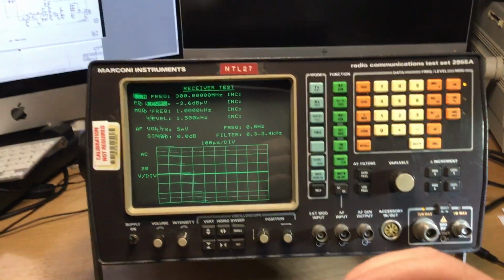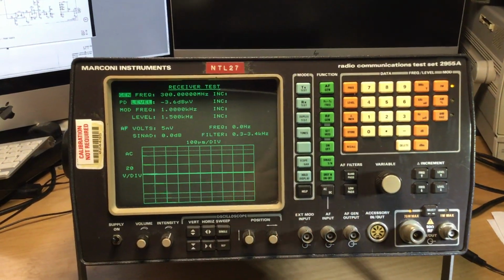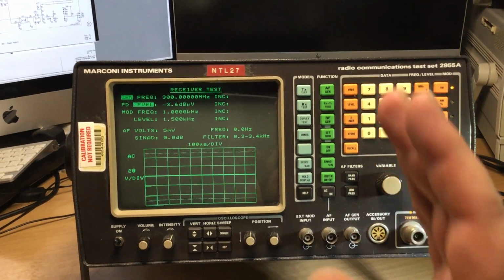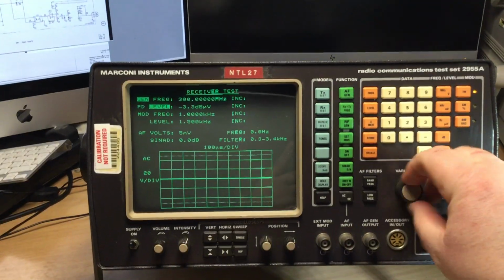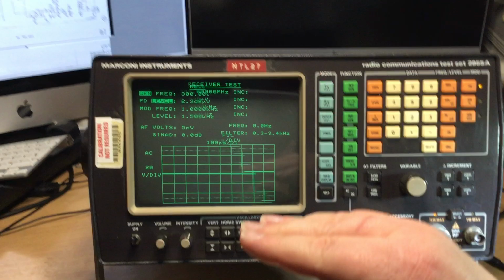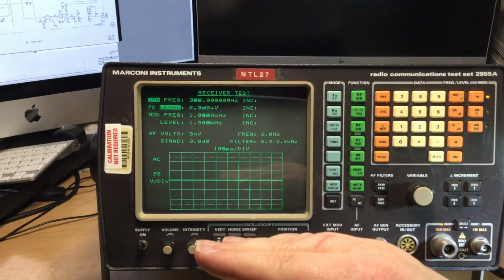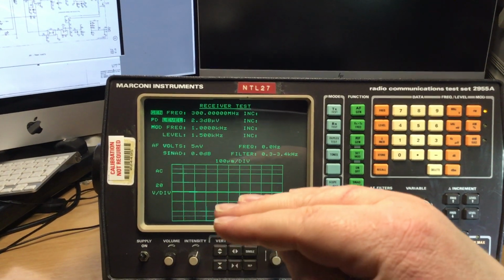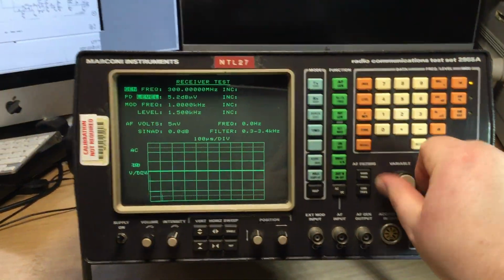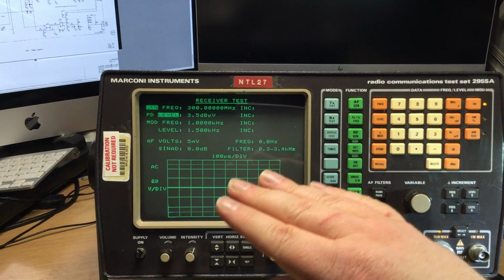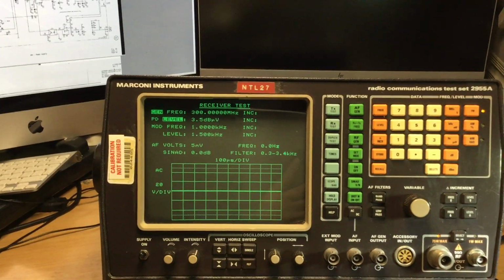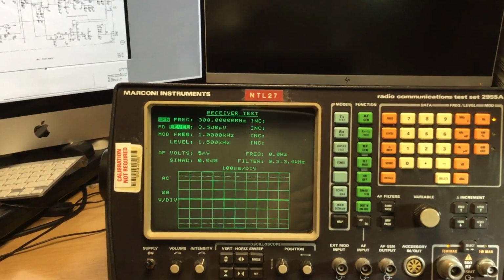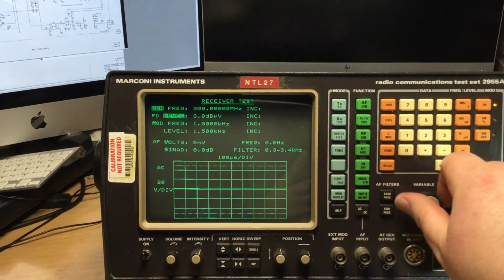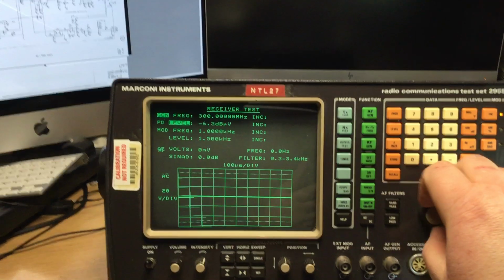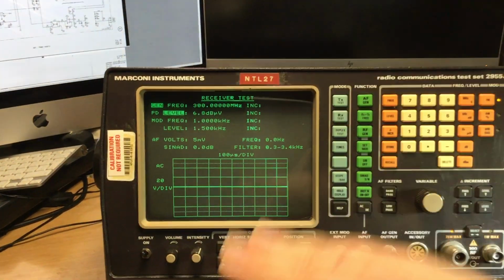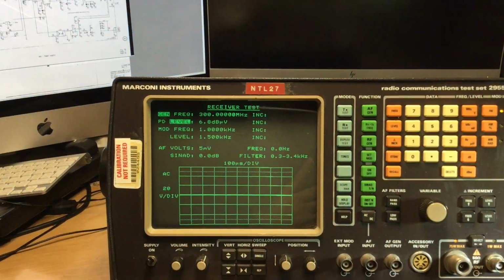But the pin diodes, there's a pin diode attenuator on the signal generator board, which is controlled by the microprocessor with a DC level, and as we adjust the rotary control on the front to a different RF level, in between the steps of the mechanical attenuator, the electronic attenuator, which consists of pin diodes, has a DC control voltage applied to it, and that depends on where we are with the control on here. And that level then changes the attenuation characteristics, the RF attenuation characteristics of the pin diode attenuator, and that's how we get the RF level to change between the physical mechanical steps. So we get a linear sort of control of the RF level, a fine control of 0.5 dB steps or whatever right the way through its level.